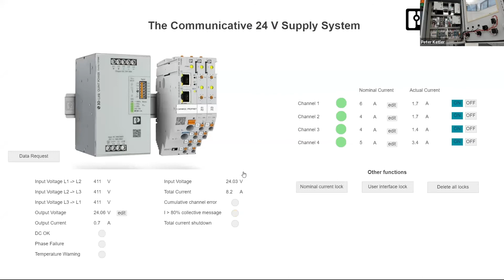So what Peter just did in the application, you may have heard the clicking sound, is the phase failure detection. Below here you see the phase failure which is detected, and with that the power supply immediately communicates that one phase is failing, and this can be forwarded to the PLC.